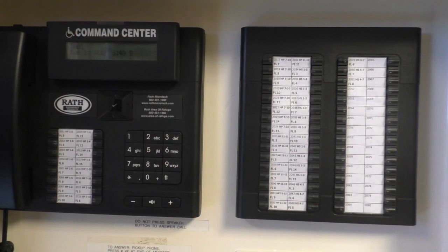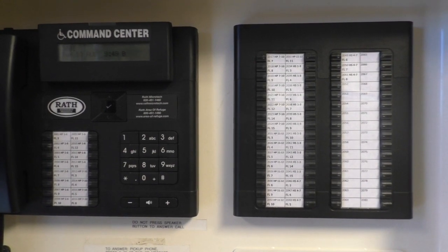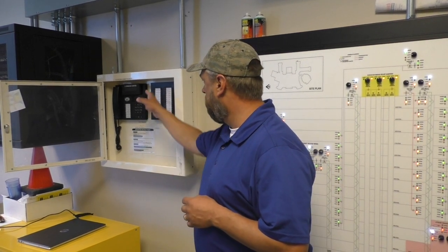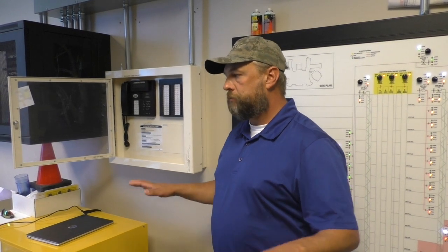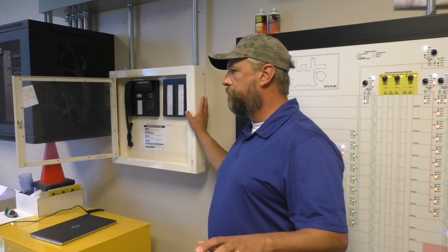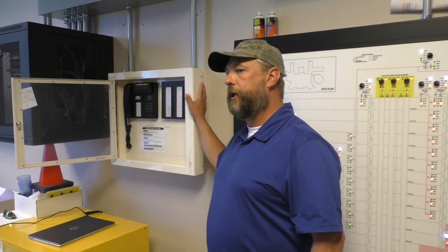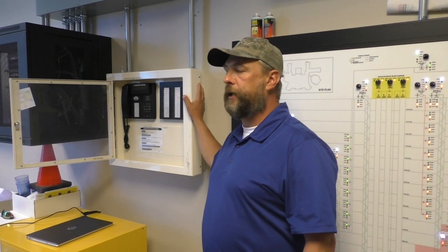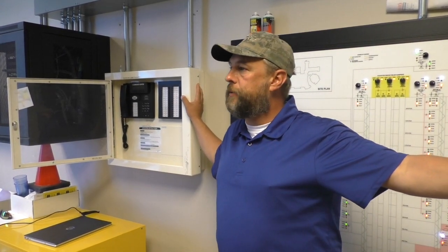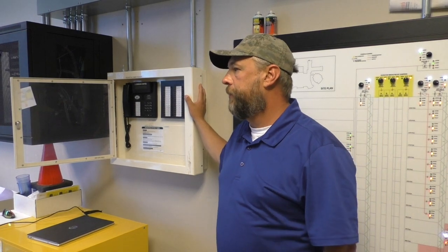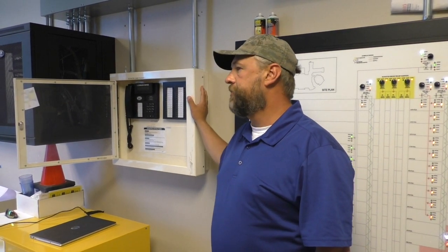If you see any LEDs on, a blue light means you're online, a red light means you're on hold, and flashing means it's talking to the monitoring center. That will be on per floor, per call box. The only time this is monitored is if it loses phone lines or backup battery. We're going to see an alarm supervisory come on for the fire alarm system. Other than that, there's no history.